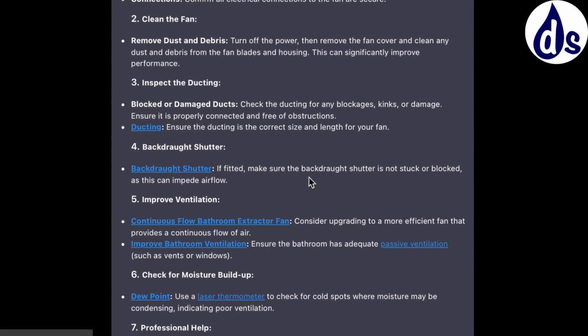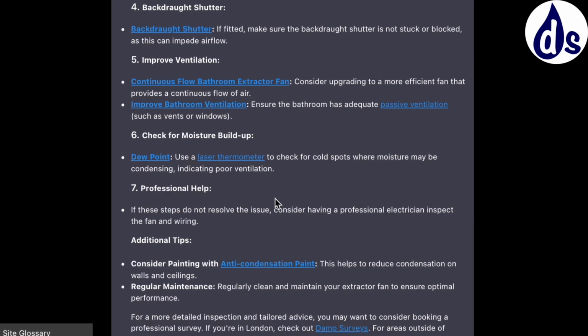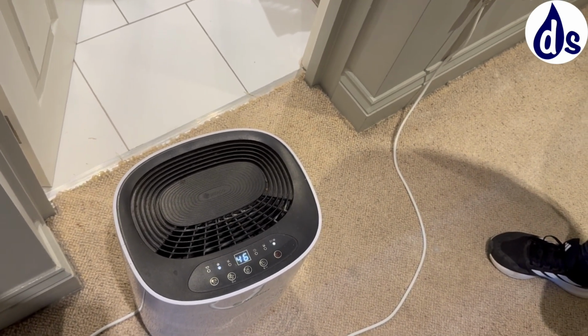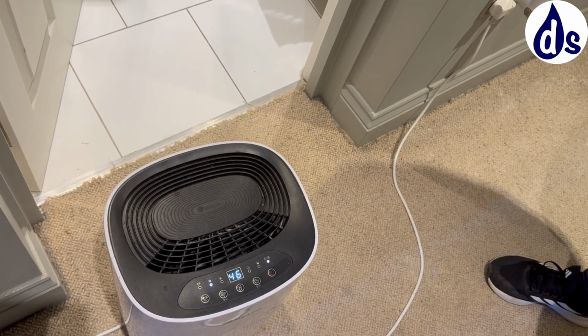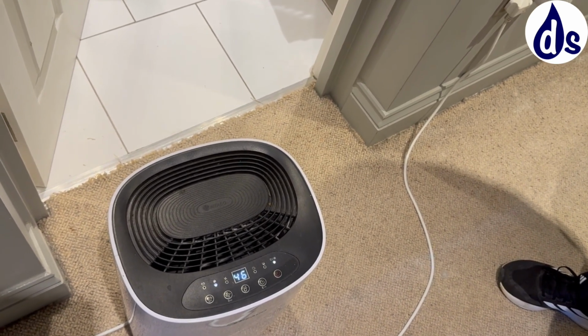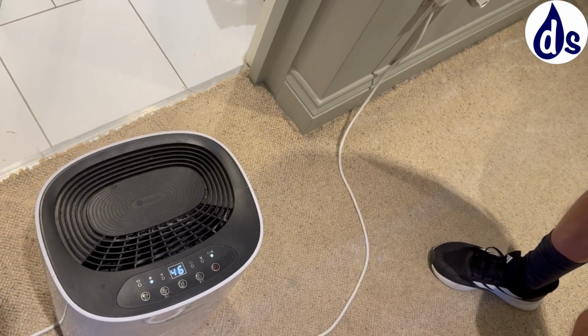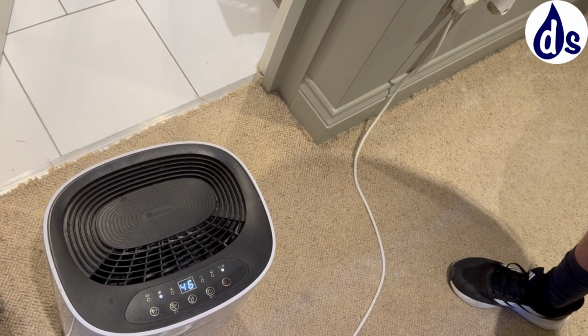The three things to know about dehumidifiers: one, you're getting rid of vapor, and it's the biggest cause of dampness in properties. About 85% of all damp issues are caused by excess vapor. Second one is that all the energy comes in as heat, or comes out as heat, plus a 50% bonus, because as you're going from the vapor to the liquid phase, you release energy.